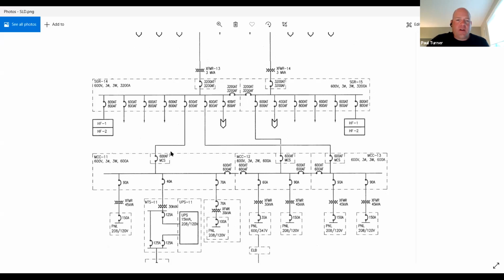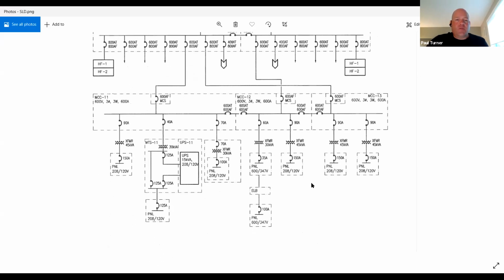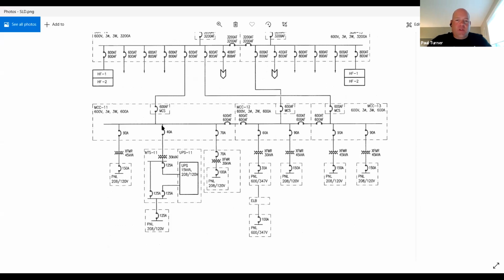Very similar, there's a tiebreaker there. The two incoming breaker feeds are closed to energize the 600 volt bus of the MCCs, followed by breaker closure of each individual MCC, which could be a breaker or a fuse, to each panel board throughout the plant systems. So there would be multiple MCCs throughout the plant process. There might be one set of MCCs in one area of the plant, and then the switchgear feeds another MCC lineup in another area of the plant. From the MCCs, there could often be additional step-down transformers to provide 208, 120 volts, or 240 volts, whatever voltage is required in the country that you're operating in, to provide power to the various panel distribution boards throughout the plant.